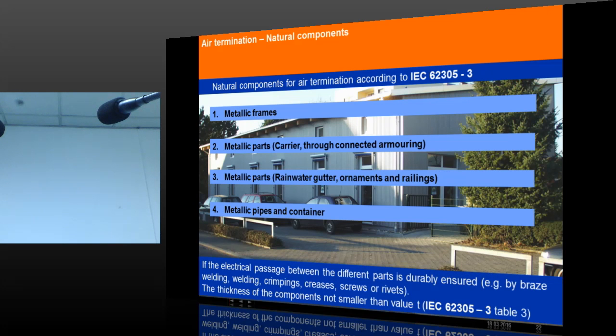Now, if you have a PE building, a pre-engineered building, or a steel structure which has a steel sheet at the top, do we need an air termination? This question we can argue in several ways, but generally, if your roof is thick enough to handle the energy effects, you don't need an air terminal, because the sheet itself is a good conductor. It will take care of the lightning current, provided it is connected to the ground.